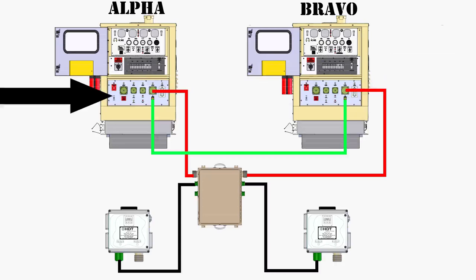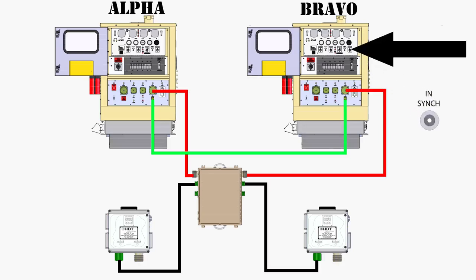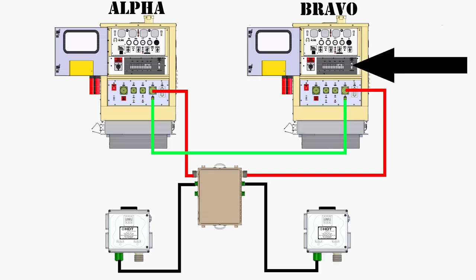Place the single parallel switch on Alpha to single and place the same switch to parallel on Bravo. Next turn the synchronizing switch to on. When the in sync light illuminates turn on circuit breaker 8 on Bravo.